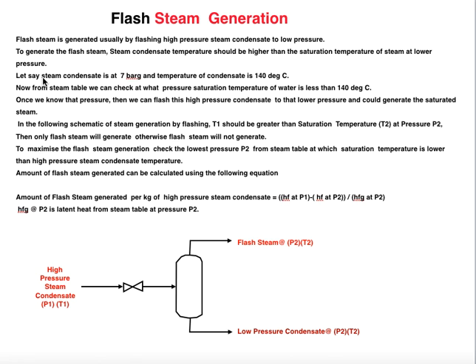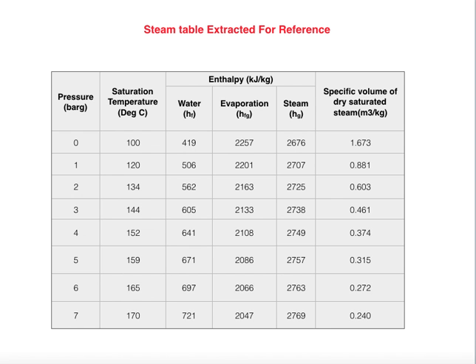For example, if steam condensate is at 7 bar gauge and temperature is 140°C, we check the steam table for pressures where the saturation temperature is less than 140°C. At 2 bar gauge the saturation temperature is less than 140°C, as is 1 bar gauge and 0 bar gauge — so we can choose P2 as 2 bar gauge, 1 bar gauge, or 0 bar gauge.